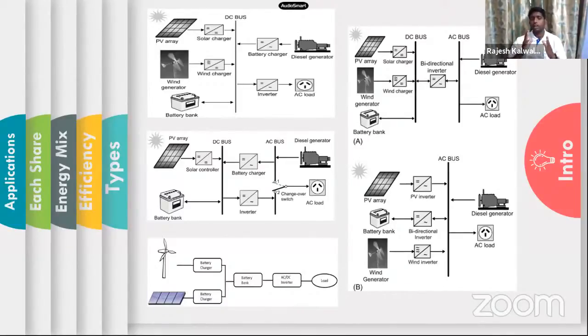It converts and gives it to the DC bus, and charges the battery. But when you have a diesel generator, you can directly feed it, because you have a changeover in between. So directly you can feed to the load, or directly charge the battery using a battery charger.